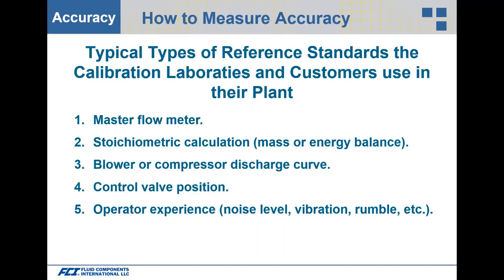Regarding reference standards, in a laboratory or calibration facility we typically use a master flow meter — a DP meter or a turbine meter. When installed at a customer site, customers typically use stoichiometric calculations: what goes in must equal what comes out — mass or energy balance, blower or compressor discharge curves, control valve position, and even operator experience.